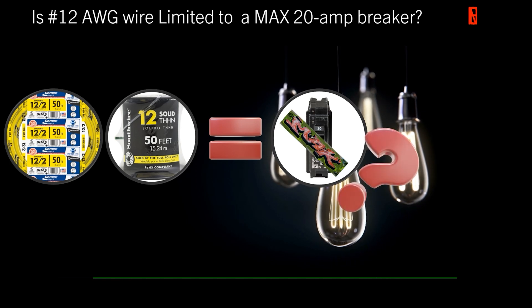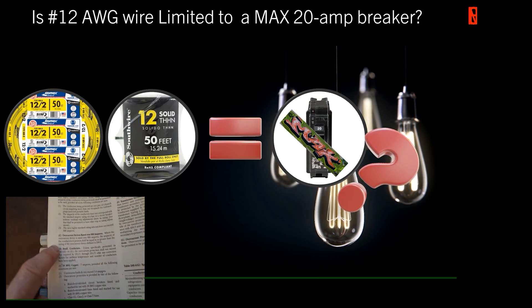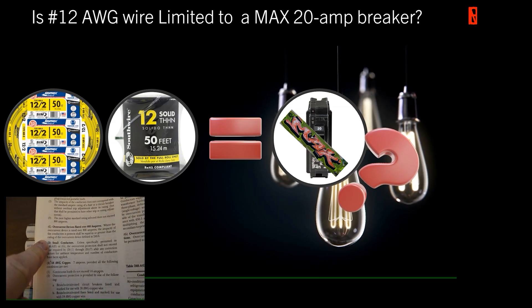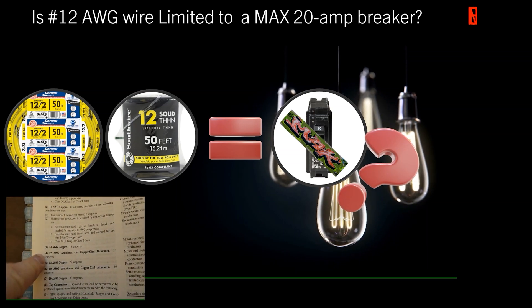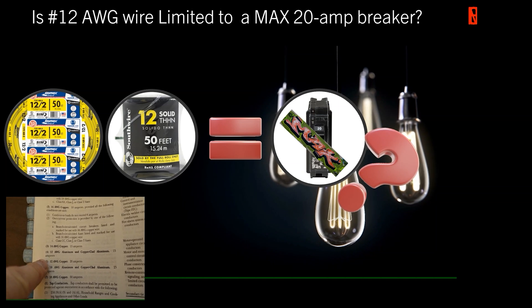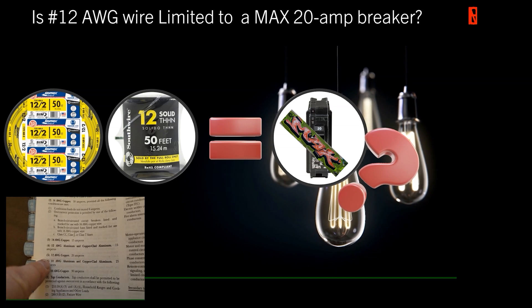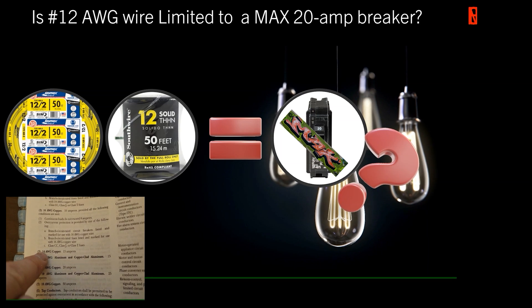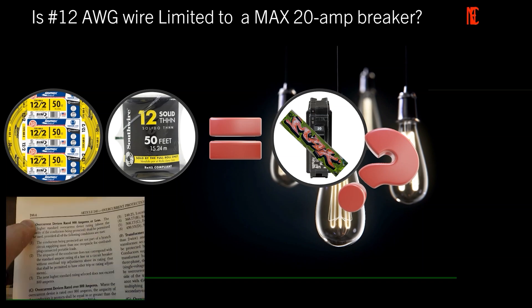This does spawn from 240.4 part D, and that is actually dealing with small conductors. It does specify that when you're dealing with conductors 18 through 10 gauge, there are some limitations as far as overcurrent protection. 12 gauge is one of them, so it's limited on copper to 20 amps. Same thing when you get down to 10 gauge, it's limited on copper to 30 amps. When you jump back up to 14, it's limited to a 15 amp breaker.